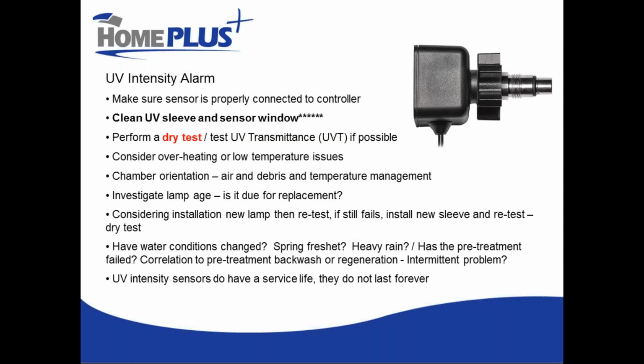So if you have ultra-fine sediments that are passing through your pretreatment and you shut the water off at night, there's no water running, that sediment will tend to settle on the little window of your sensor when it's oriented on the bottom. So give some consideration to your chamber orientation if you're seeing frequent intensity alarms. You can always try installing a new lamp and sleeve to see if it makes a difference.